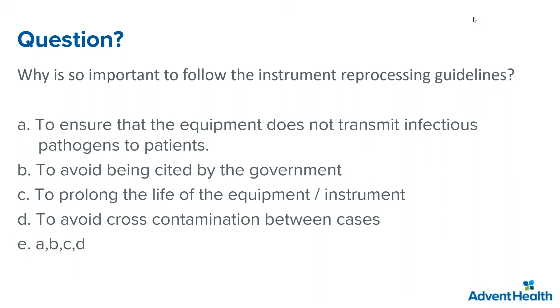So let's look at the process. Once the instruments are in the area that is going to be reprocessed, now we have what is called a washer disinfector. Let me tell you, many moons ago, you had two hands, and that was your washer disinfector. Before, we used to do everything manually. Now they manually pre-clean, and then everything goes into the washer disinfector. After pre-cleaning, all the instruments are appropriately placed inside the washer disinfector, the hinged instruments are open, and the instruments are disassembled if indicated by the manufacturer.